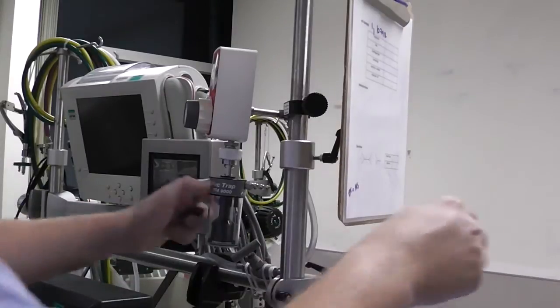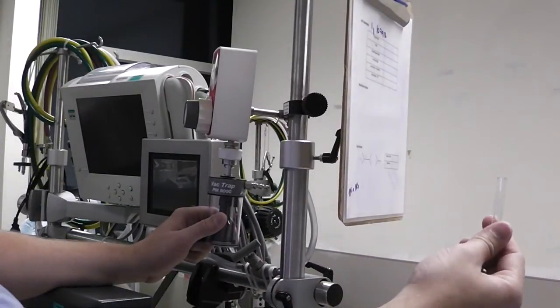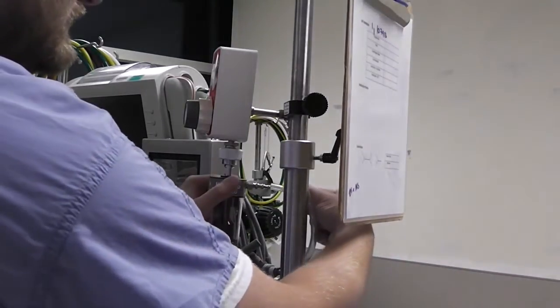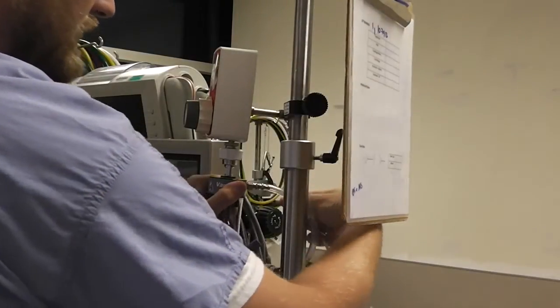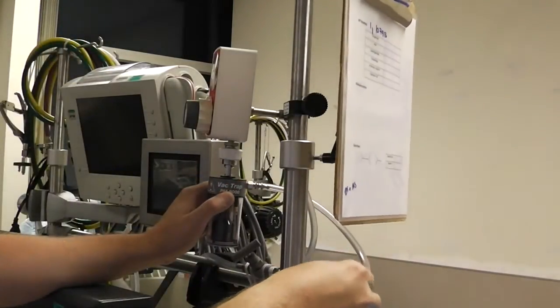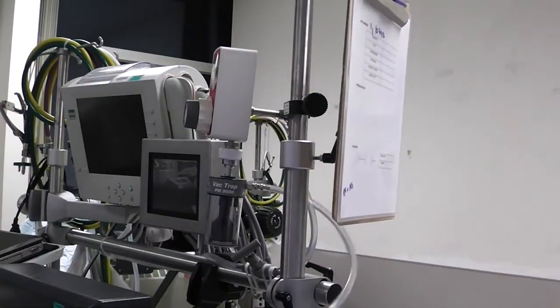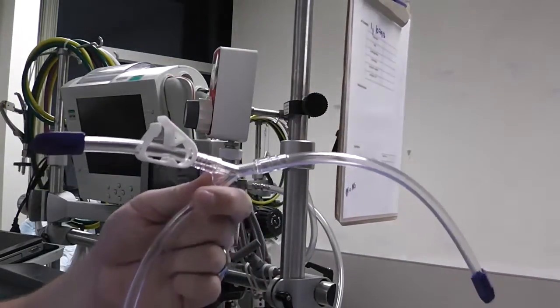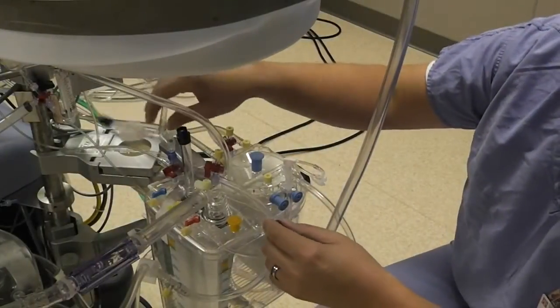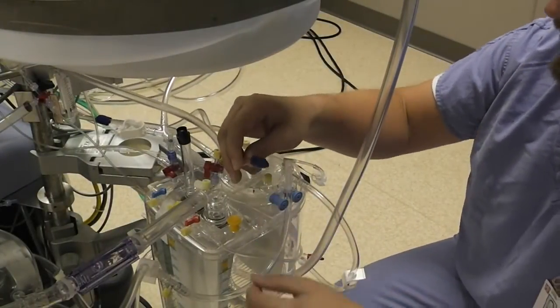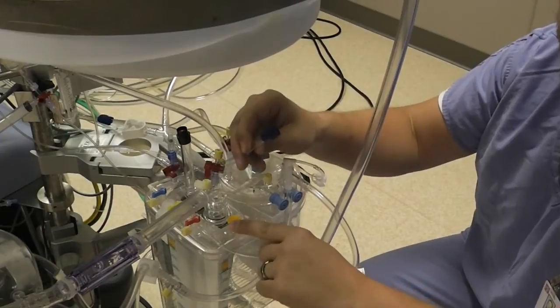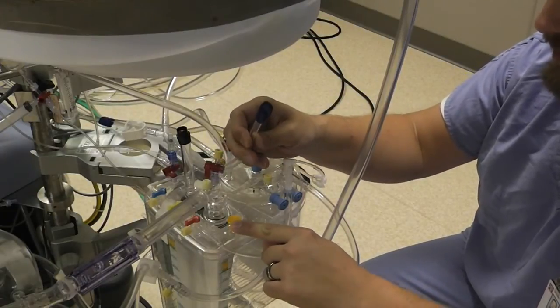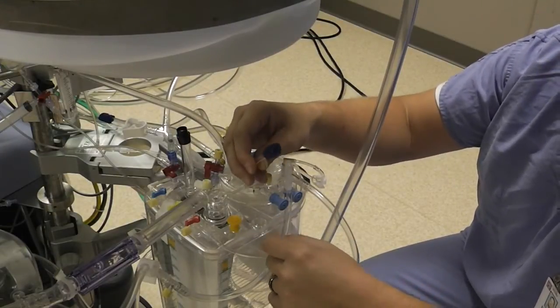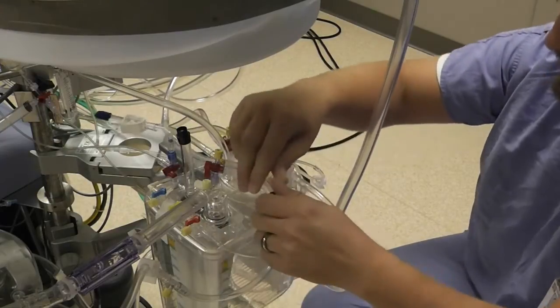And I'm actually still in the front of the pump. Normally I would do this from behind, but just to make it easier for me to not have to move the camera around as much. That will connect like that. And now we'll take this end down and make the connection at the top of the reservoir. So here I have the other end of the vacuum line, and this is a vented cap that's on the top of the reservoir, and this is where we're going to attach the other end of the vacuum line.